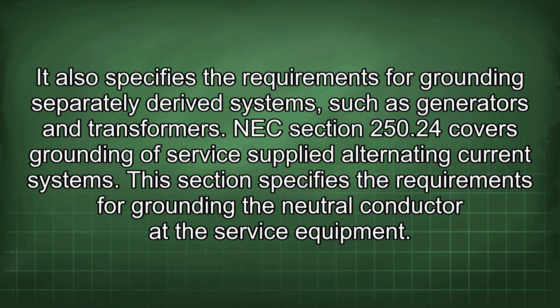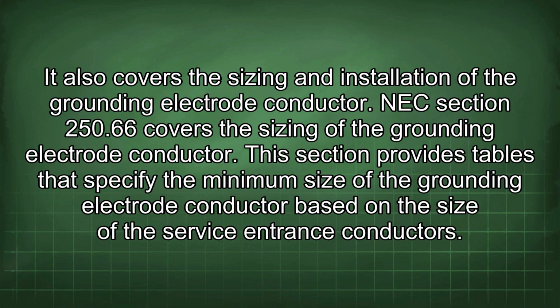NEC Section 250.24 covers grounding of service-supplied alternating current systems. This section specifies the requirements for grounding the neutral conductor at the service equipment. It also covers the sizing and installation of the grounding electrode conductor. NEC Section 250.66 covers the sizing of the grounding electrode conductor. This section provides tables that specify the minimum size of the grounding electrode conductor based on the size of the service entrance conductors.